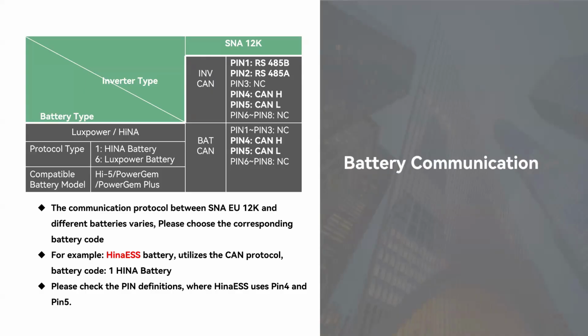And for the battery communication, firstly, let's look at the pin definition of the SNA 12K. As you can see, pin 1 and pin 2 is for RS485, and pin 4 and pin 5 is for the CAN communication. We have different battery codes for different battery brands. For example, the Hina battery is battery code 1, LuxPower battery is battery code 6, and all of them use the CAN protocol with pins 4 and 5, which is the same as the inverter. So we can just use pass-through cables to connect between the inverters and the batteries. And if the pin definition of the battery is different from the SNA, we might need to rearrange the cable to ensure the communication.